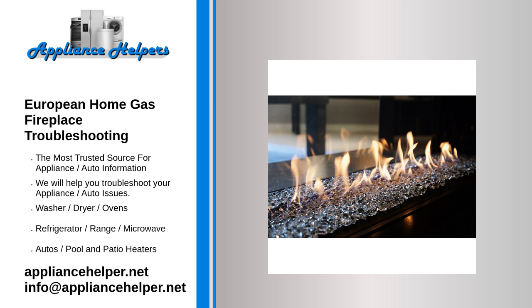Low voltage from the thermocouple. Replace thermocouple. Do not over tighten: hand tight plus 1/4 turn maximum. No gas, magnet unit drops after the 30 second audible count. Check gas supply. Too much primary air. Reduce the primary air opening until flames have a blue base and yellow upper 2/3.